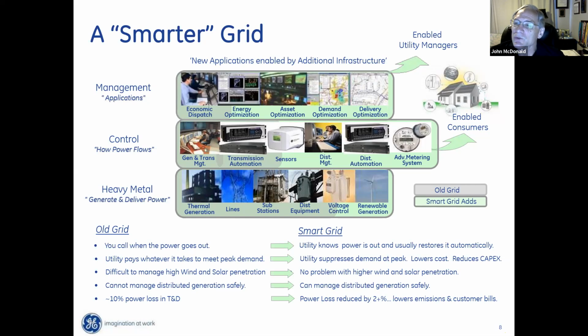Likewise, when we control the capacitor banks and the voltage regulators on the distribution feeders, we reduce losses, right? That's reactive power control, or power factor control, or VAR control. We've always done that separately. The problem is, when these two are done separately, they can negate or reduce the benefits of each other. When I switch a capacitor bank on a distribution feeder, the voltage rises at that point on the feeder, which could be a problem for voltage control, right?